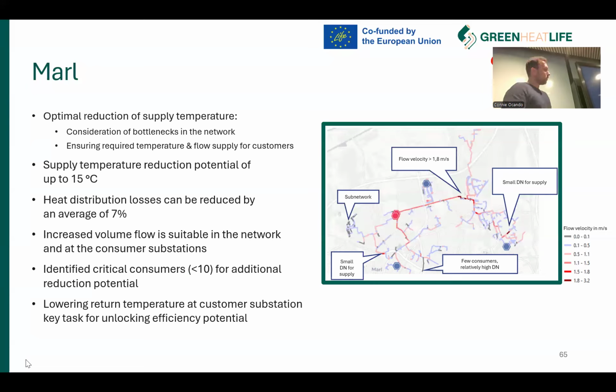One point to mention further is that we also experienced that the return temperatures of the substations are the most critical points. When we're reducing the return temperatures, we then also do not need to increase the volume flow as much. We additionally identified the most critical consumers that limit even further temperature reduction.